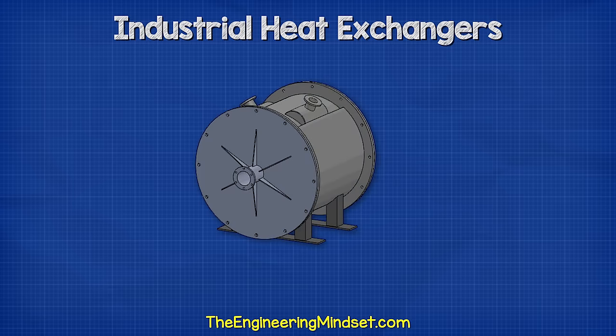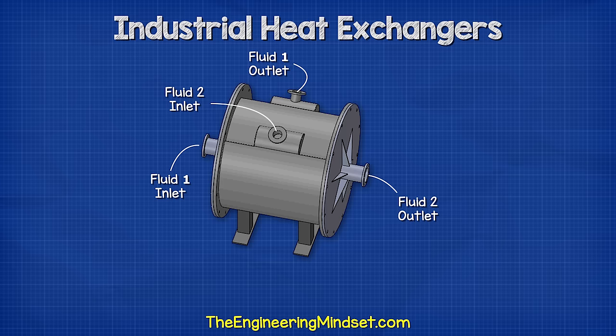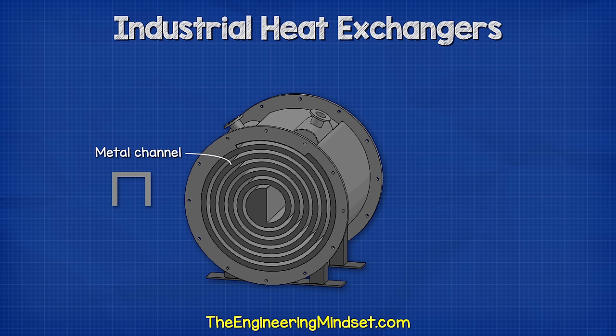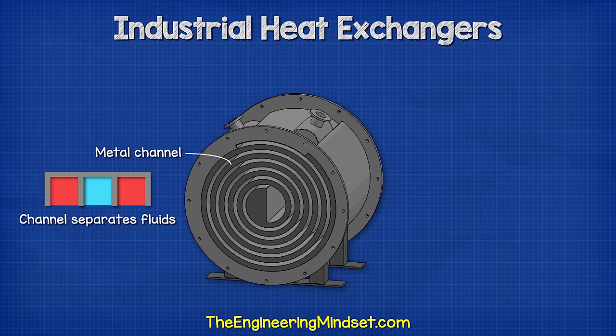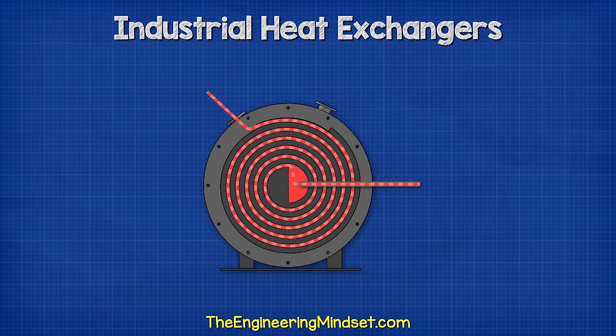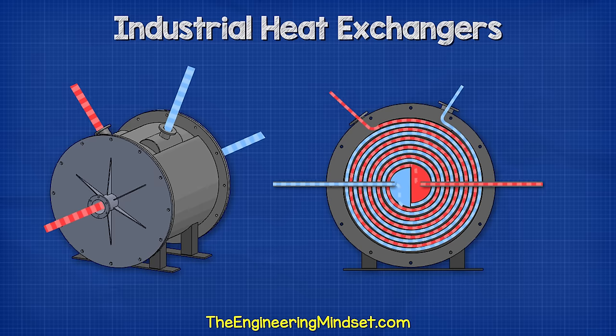Spiral heat exchangers look something like this. We have a flanged inlet on the front face with the outlet on the top, then another fluid's inlet also on top with its outlet on the rear face. Behind the end plates, two sheets of metal spiral together around the interior to form a channel through which the fluids flow. The channel completely separates the two fluids. The first fluid enters the heat exchanger, fills the chamber, flows around the channel, and exits. Meanwhile, the second fluid enters via the top, flows around the channel, into the chamber, and exits. The two fluids enter and exit at different temperatures.